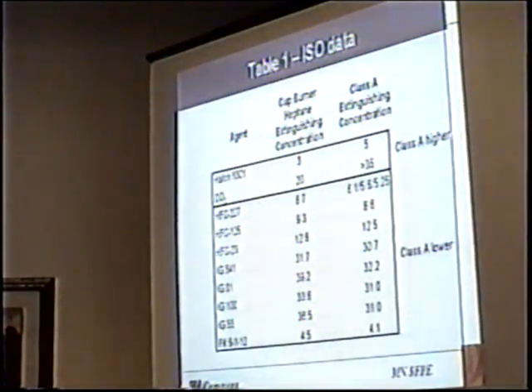That's what competition will do for us. And because basically with Halon, they didn't really push too terribly hard. If you look at the Class A values, you can probably take Halon down to less than 3, maybe 2.5% concentration. CO2 definitely as well, same thing. But with these, much testing went on over the last 10 to 15 years to take those concentrations and drive them down to the lowest common denominator. And that's basically what's occurred there.